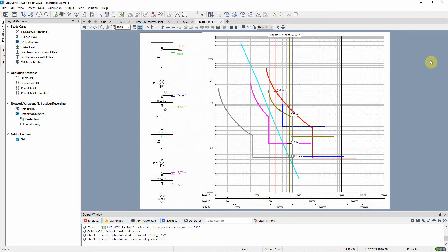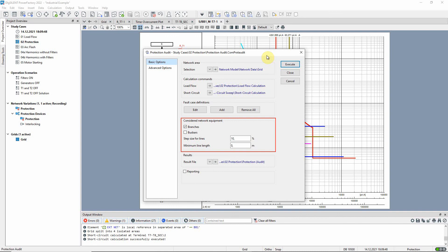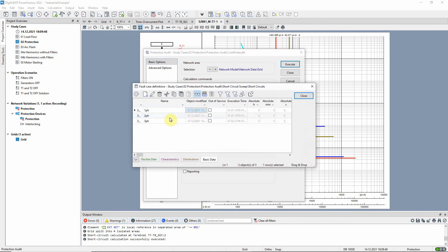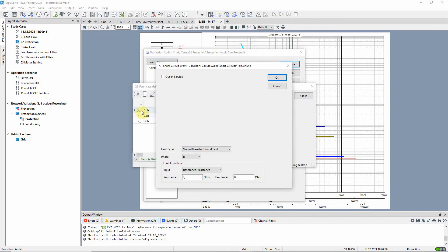To assess the whole network like this could be very time consuming. A more efficient method is to use the protection audit function. The grid or part of the network to be audited is selected and short circuit calculations at 10% intervals along the lines will be carried out. The required short circuit definitions have already been added.